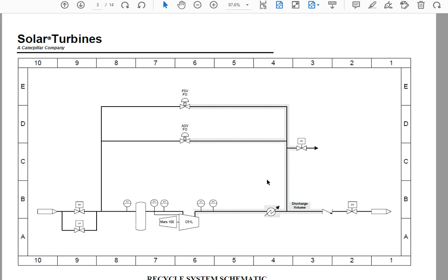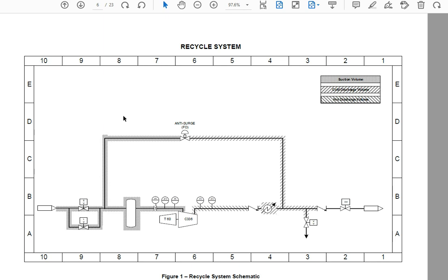The downside of this arrangement is that you're still dealing with a really large discharge volume. You've got a lot of gas to move back to suction, and you're going to have large pipe sizes to keep the velocities reasonable through this recycled network. So this was used frequently, maybe in the aughts on to maybe 2010-ish. This design had been used forever, up until people realized that fast stop surging is a common problem.